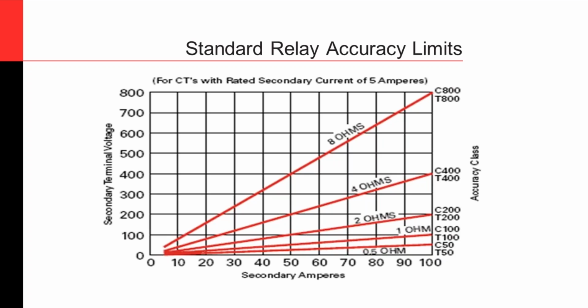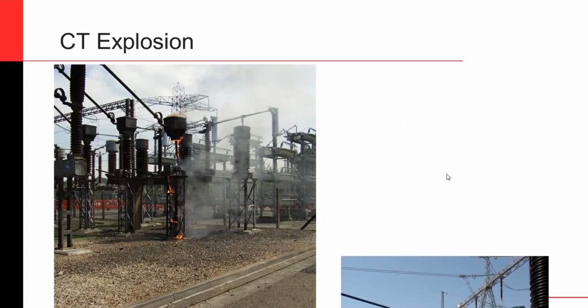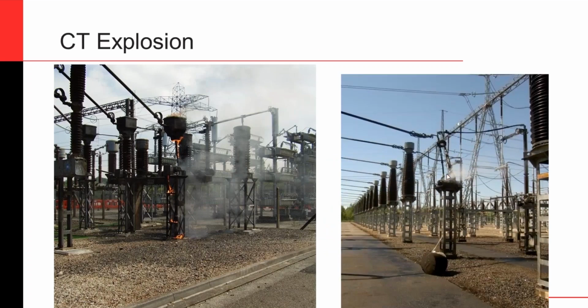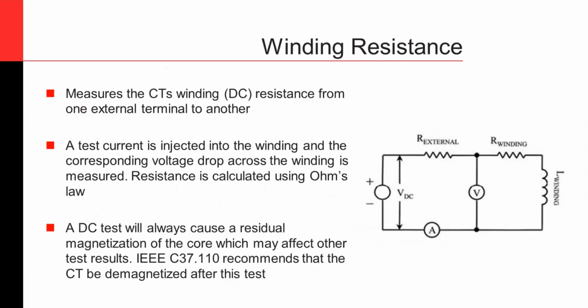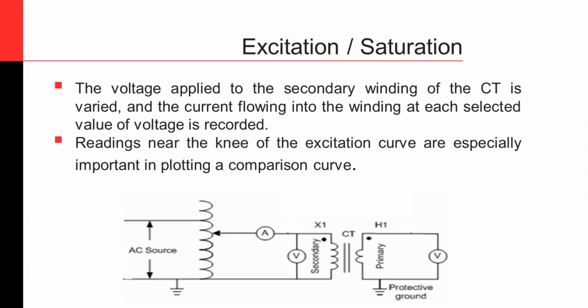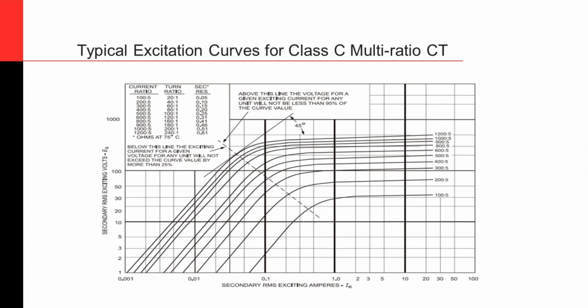For C400, no matter what your excitation current is, or the current through the primary is, or the induced current on the secondary is, man, I'm giving you guys a lot of options. However you want to think, primary current, higher primary current, or the induced secondary current, no matter what it is, your response from the secondary is going to be constant after a certain value. That's why it's called, hey, the CT saturated. It is not going to do anything anymore.